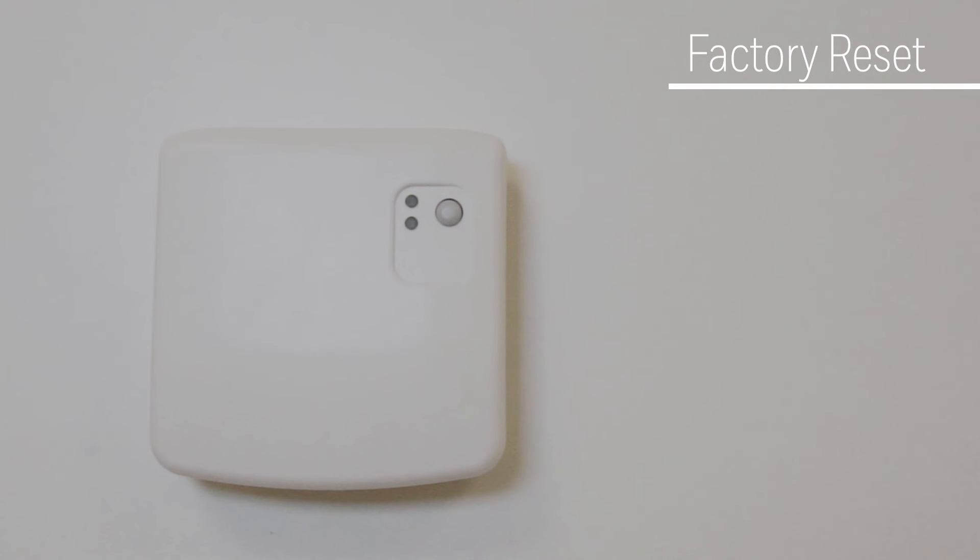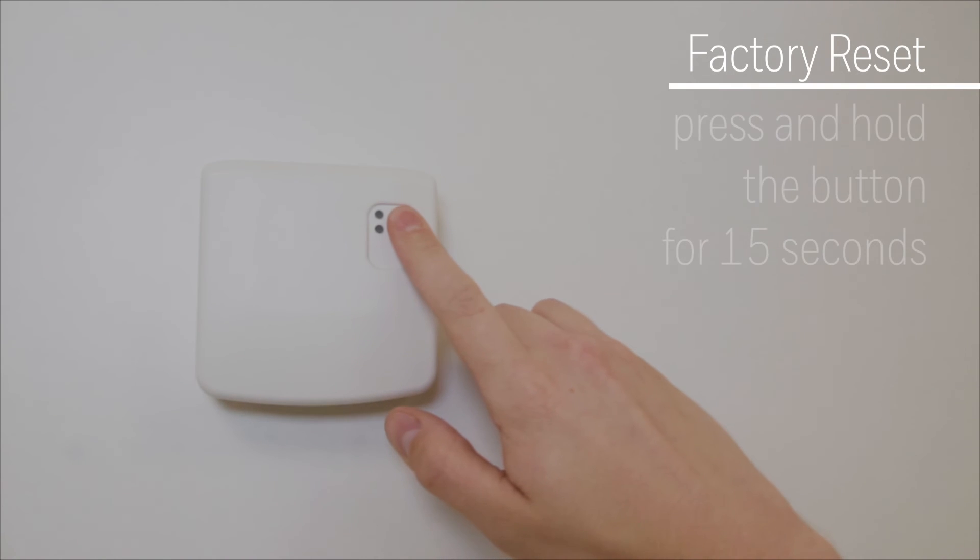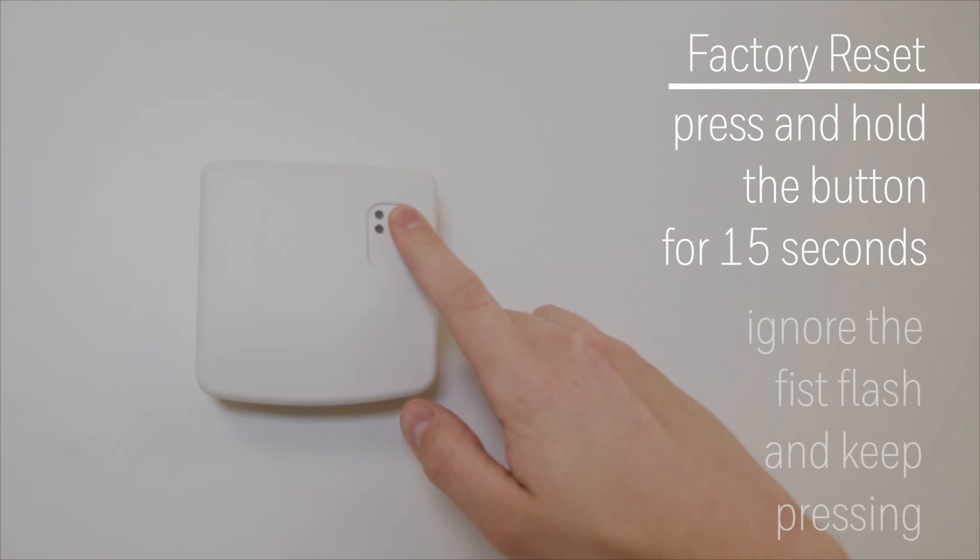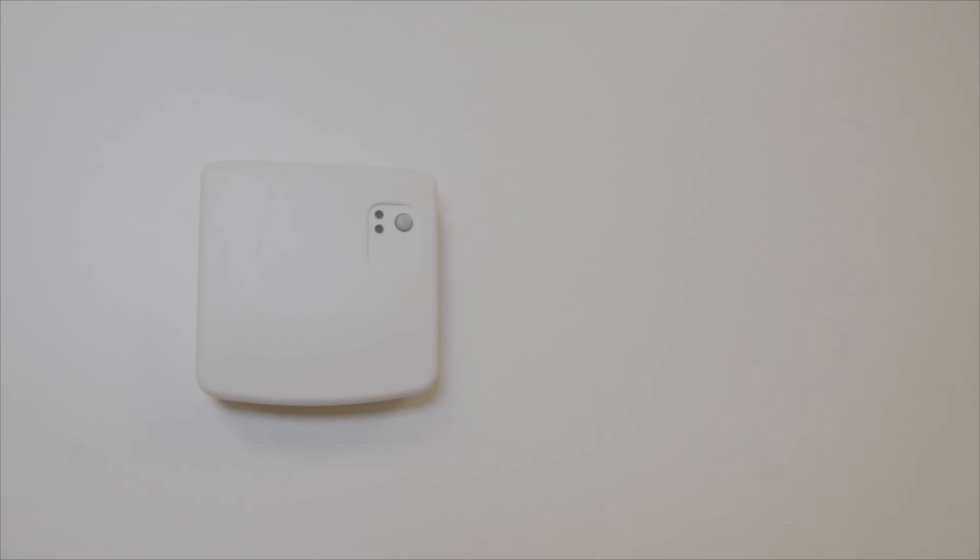The factory reset will return the unit to the conditions at first power on and delete all the bindings. This is initiated by pressing and holding the button for 15 seconds. After 5 seconds, you will notice the red flash, which indicates binding mode, but you have to ignore it and keep pressing until it blinks faster at 0.1 seconds on and 0.9 seconds off to perform the reset.